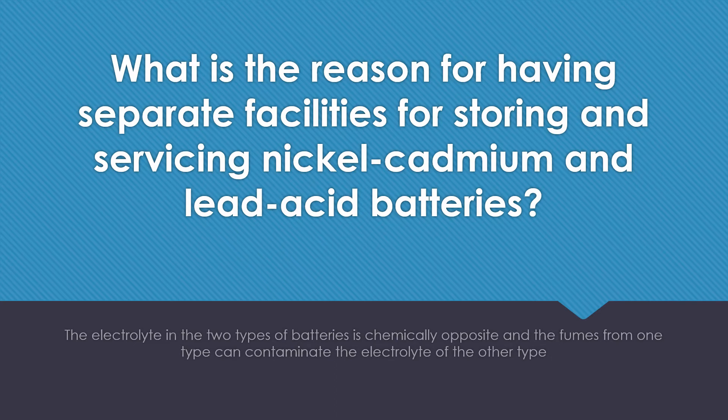What is the reason for having separate facilities for storing and servicing nickel-cadmium and lead-acid batteries? The electrolyte in the two types of batteries is chemically opposite and the fumes from one can contaminate the electrolyte of the other.